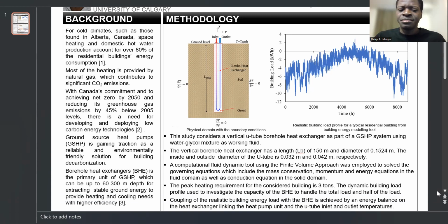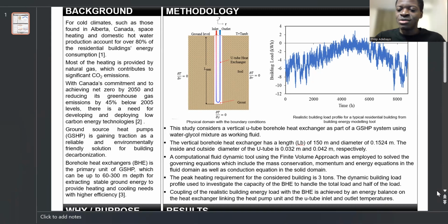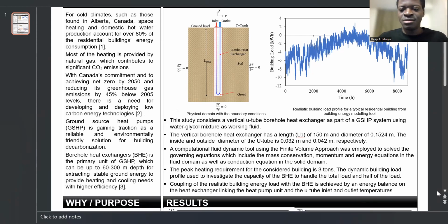Basically, the ground heat exchanger is the primary and a critical unit of a ground source heat pump, and the vertical borehole heat exchanger has been widely studied for ground source heat pump application. A vertical borehole heat exchanger can be about 60 to 300 meters deep, and it extracts stable ground energy in order to provide heating and cooling needs with higher heat pump efficiency. It can range from 400 to 600% based on a given location.